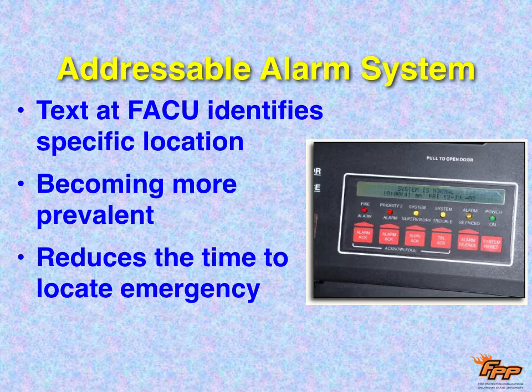Nowadays, we have modern addressable alarm systems. These are digital-based. They are way, way better than what we used to have. You get a text at the panel that identifies not only the location, but much more specific. So not just the building, the actual room and device. So it might say in the digital readout there on the top of that picture, smoke detector number 12, room 111, building J. So the firefighters are able to get to the problem. It reduces their time to locate the emergency. It's really great. They're very, very good.